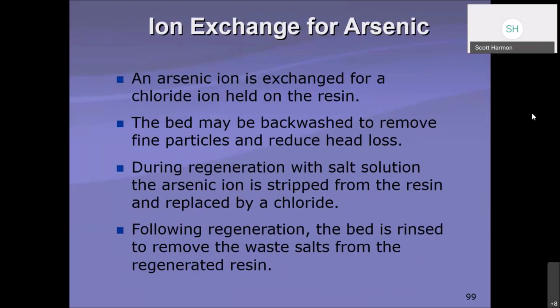When we talk about the ion exchange, we're exchanging the arsenic ion for an ion of the salt. So during regeneration with the salt solution, the arsenic ion is stripped from the resin and replaced by the chloride. Following regeneration, the bed is rinsed to remove the waste salts from the regenerated resin. So typical filter type things.